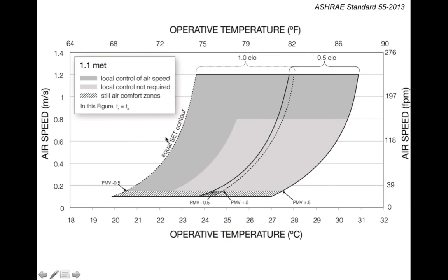But when it goes to the higher elevated airspeed range, then we are talking about local control, like a small fan in front of a person on the table, or what we talk about in the context of an air terminal device that ends on a person's workstation or work table, providing an individual air supply. So these are local airspeed control, which is the dark shaded space, as compared to the lighter shaded space where you don't need local control. A general fan would serve the same effect.